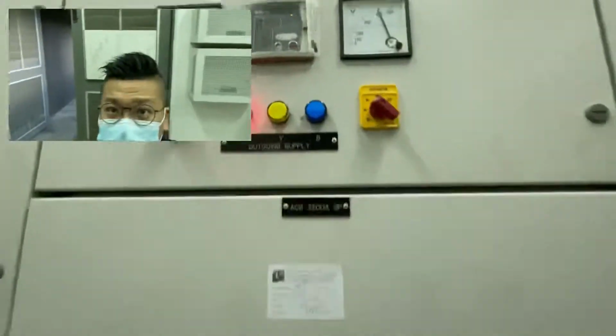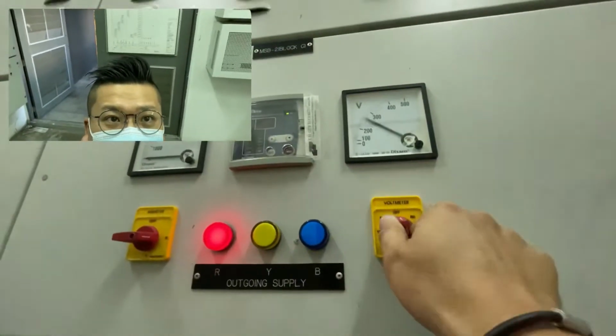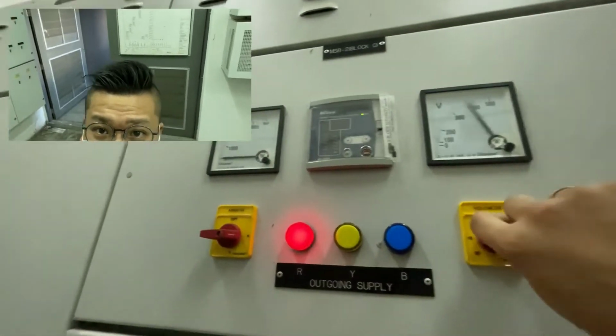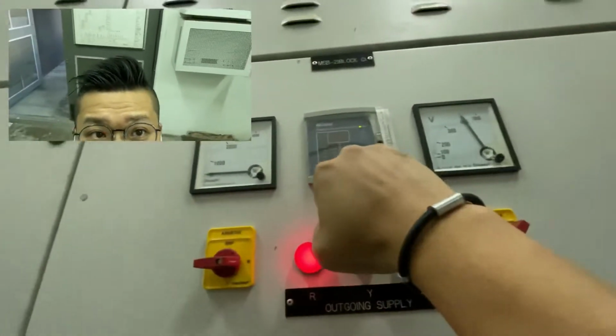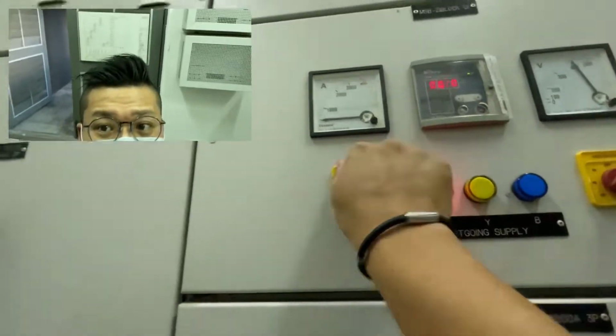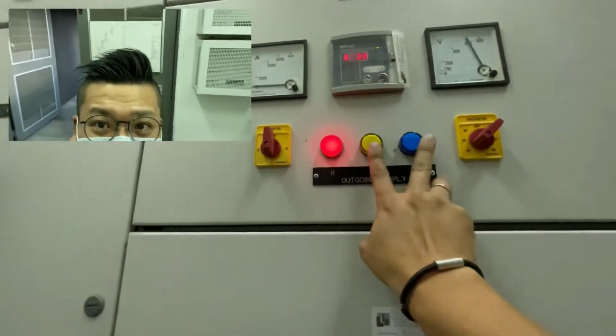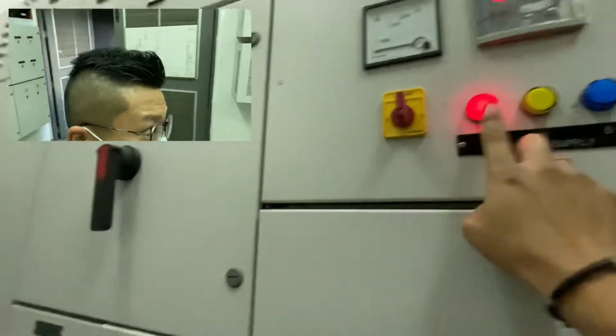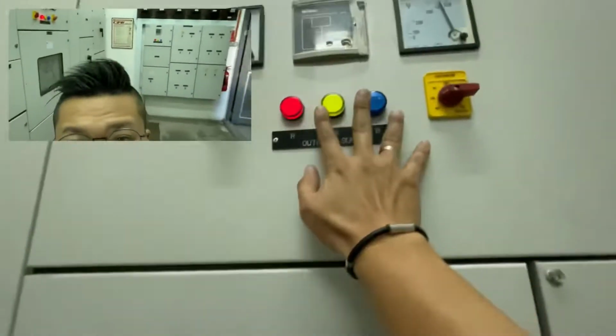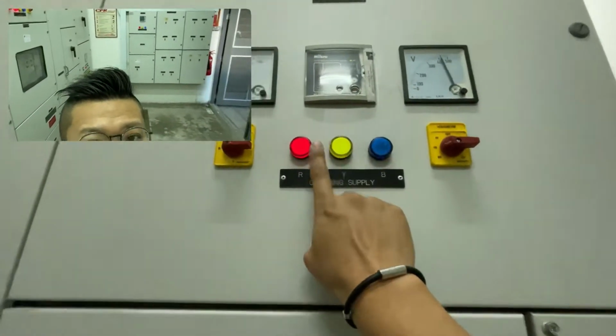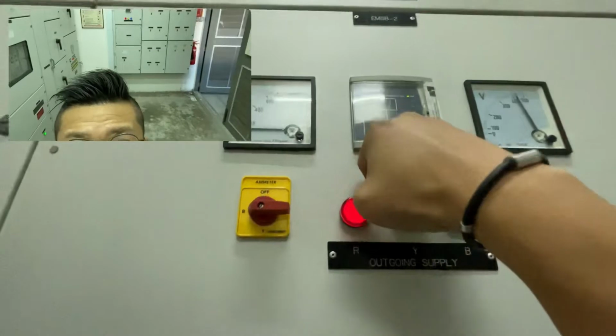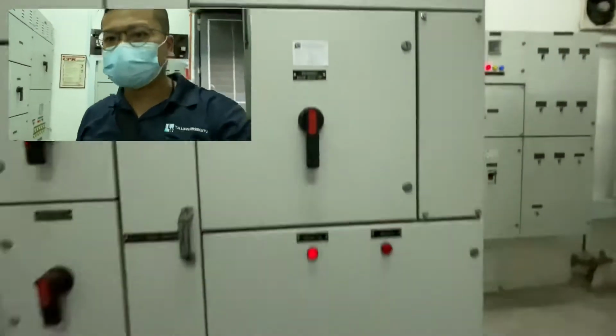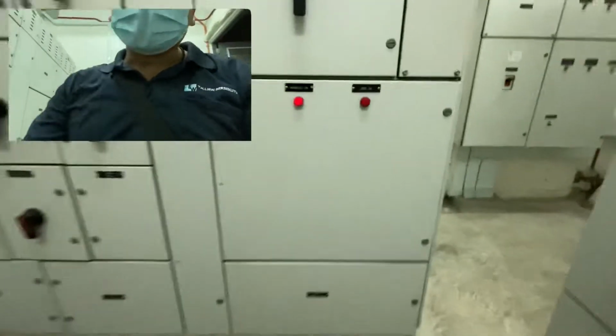Okay, let's check the voltage. Okay, voltage okay, single phase, three phase. Protection relay is in good condition. Indicator light, okay, 2 faulty, 1 is okay. Indicator light, 1 faulty, this one dim, this one okay. Protection relay is in good condition. Okay, this is a ATS.